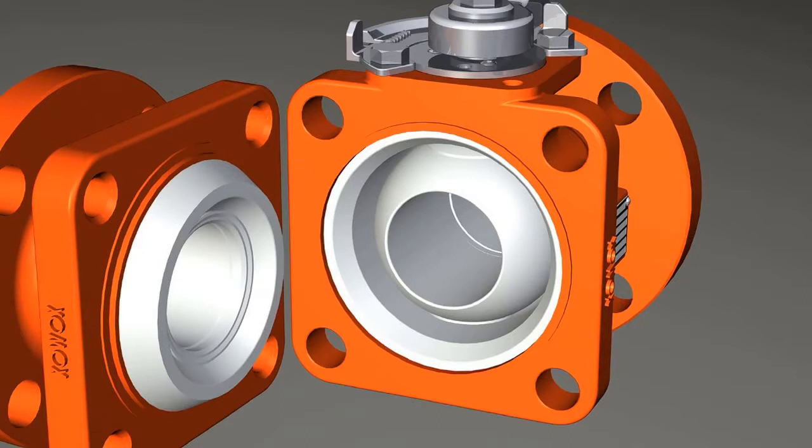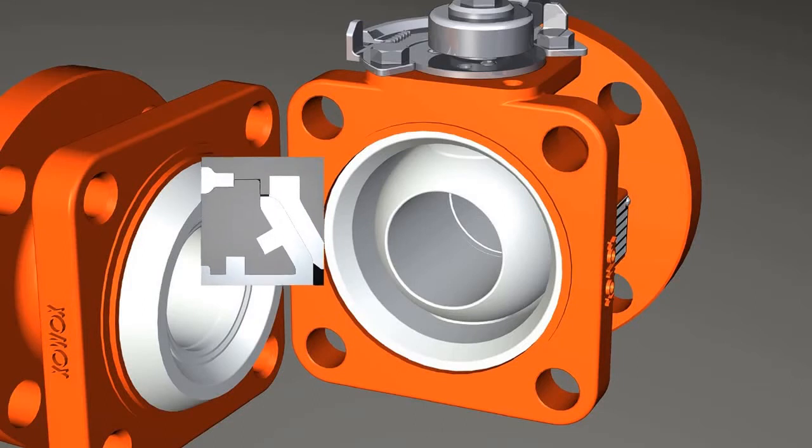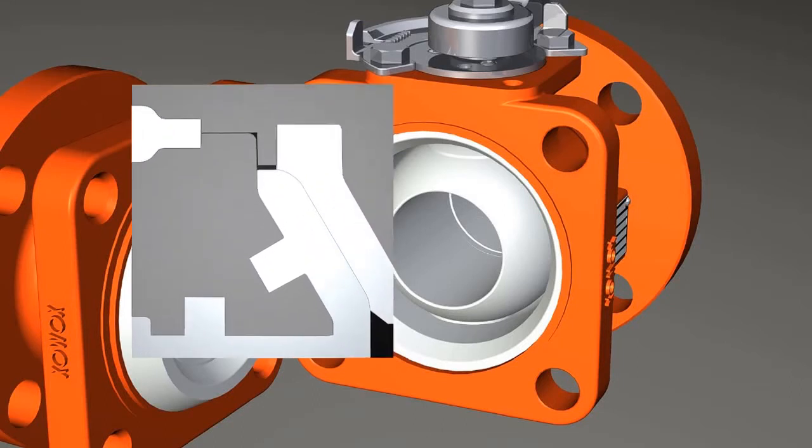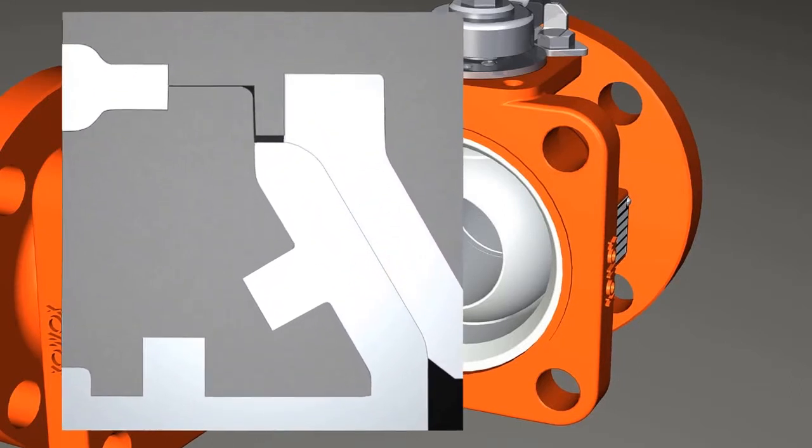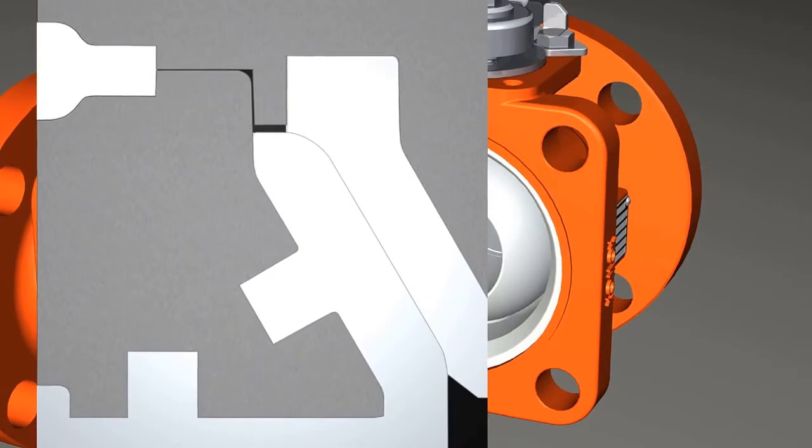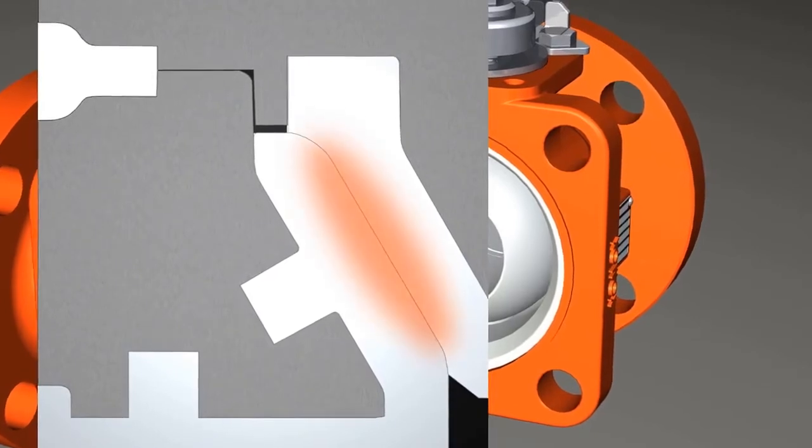In order to improve sealing, the body parts have a broad, angled contact surface. This new technology has the advantage that when temperatures rise, the expansion of the plastic liner presses the body pieces more tightly together, without deforming them.